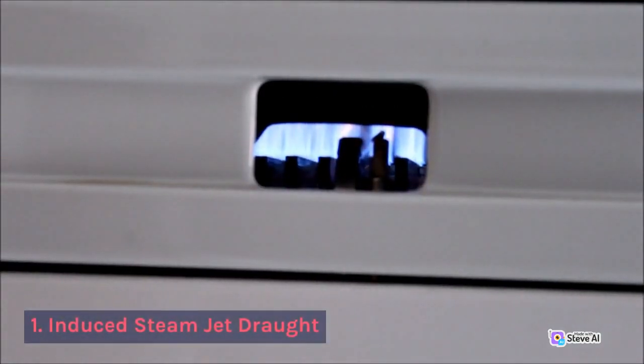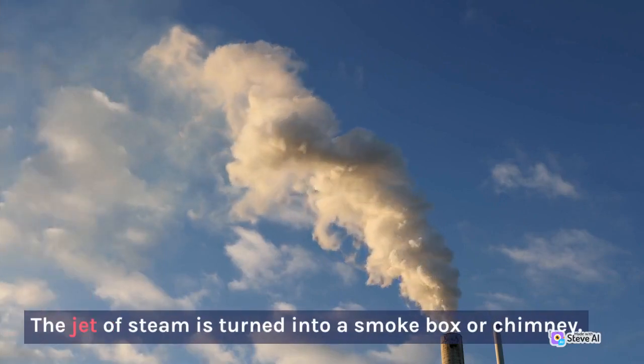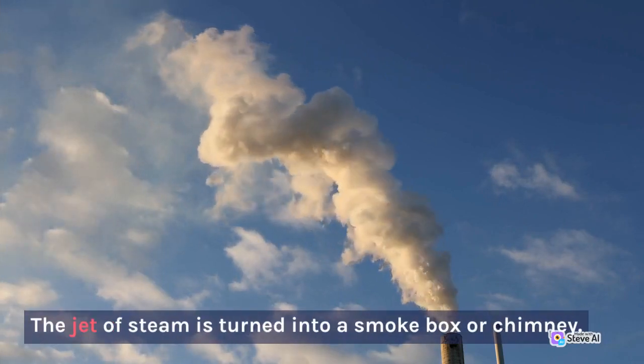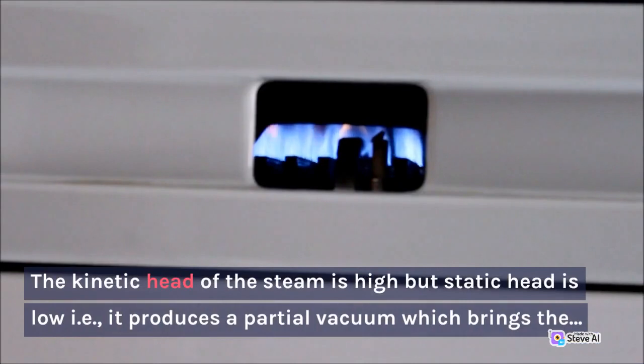Types of steam jet draft: 1. Induced steam jet draft. The jet of steam is turned into a smoke box or chimney. The kinetic head of the steam is high but static head is low. It produces a partial vacuum which brings the air through the grate, ash pit, flues and then to smoke box and chimney.